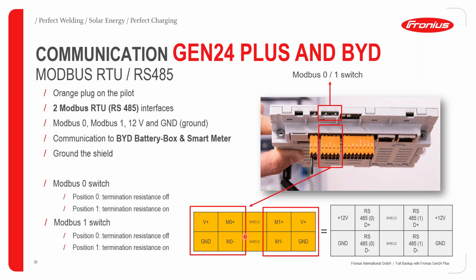So we have a diagrammatic representation of how they look. So we have M0 positive and M0 negative. This can also stand for D plus or D minus, depending on how you understand it as an installer. So as you can see in this case, it's D plus and D minus. And then we have M1 plus and M1 minus, which is the second modbus terminal. And then of course your 12-volt supply, ground, and ensure that your shields are appropriately connected.